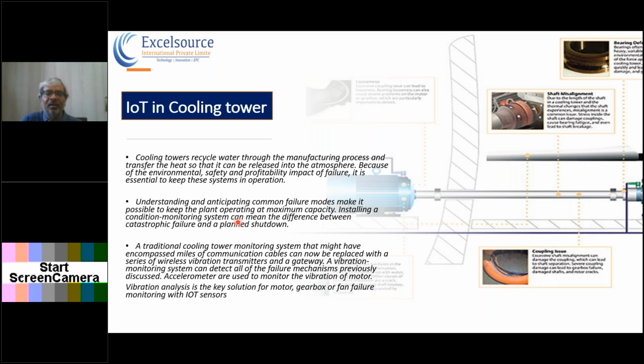This can help in identifying problems in the bearings and problems in the fan blade, which can probably cause a disaster, or a safety problem in the plant. So any vibrations happening in the motor or the shaft of the fan can be immediately identified, and we can avoid damage to the asset, and even the potential safety risk for the people working close to the cooling tower installations.